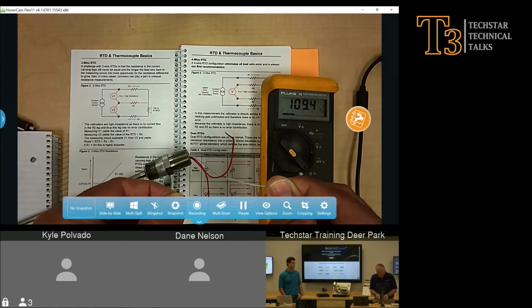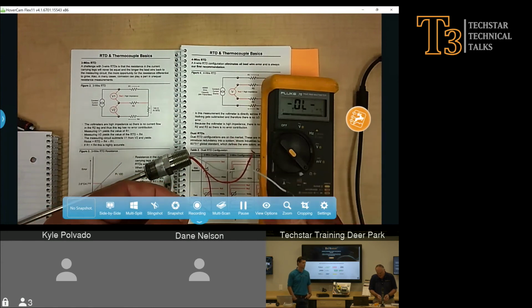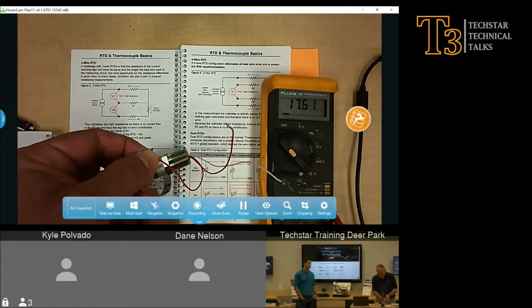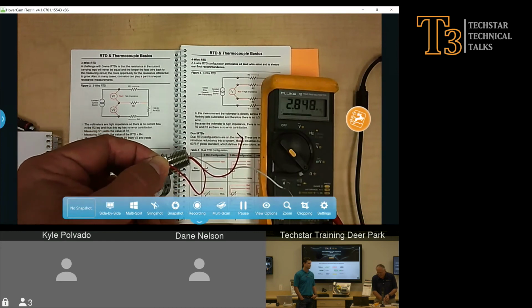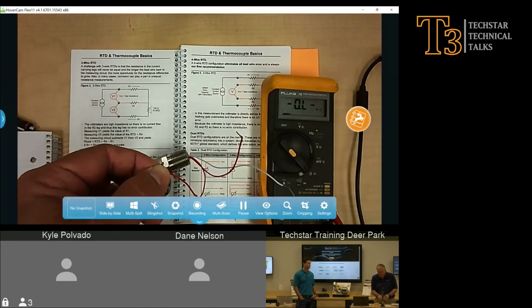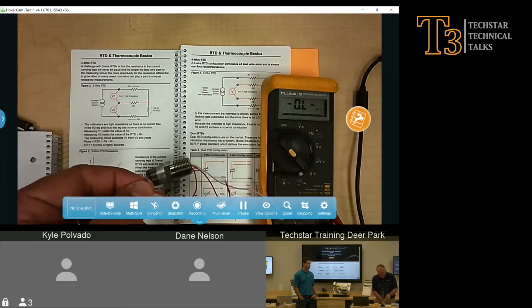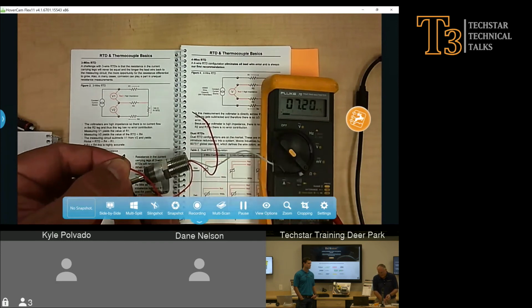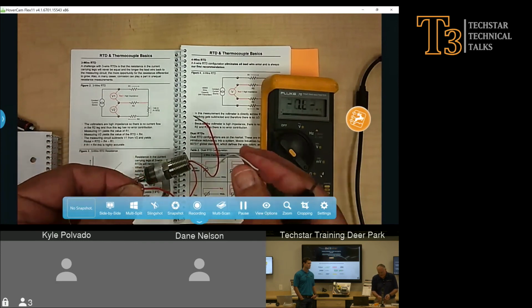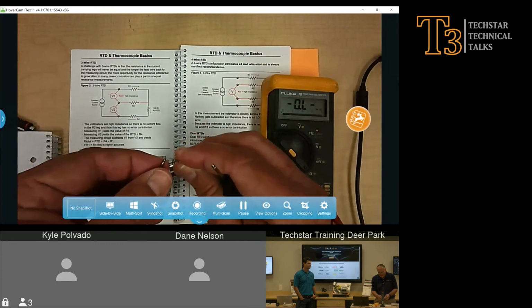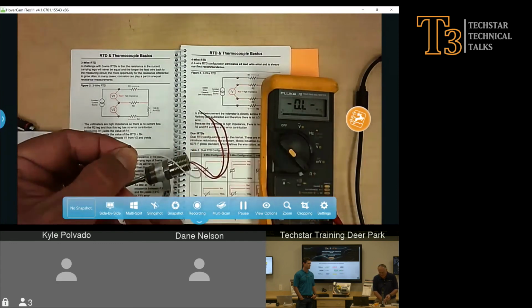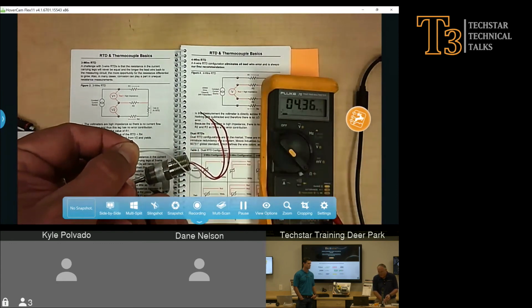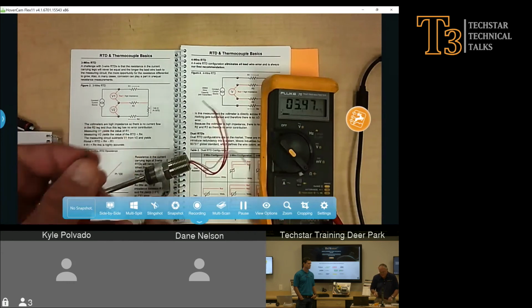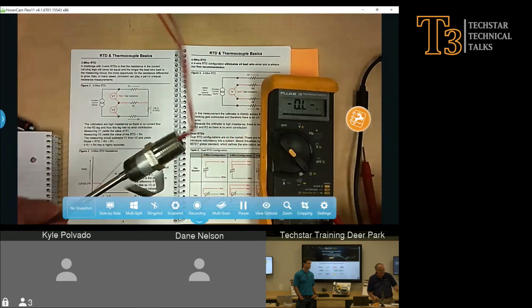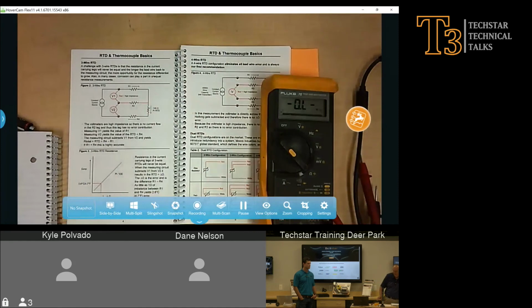Got it? Now the other thing that we can do quickly to check is I can take each of these to ground. Thermocouples, you can ground. RTDs, you can't, because it's resistance. So that's the first thing we look at. Why would it be grounded? Could have had something bad happen to it, but oftentimes in this part of the country, it just absorbs moisture. Okay, so there ends the lesson on 3-wire 385 alpha.